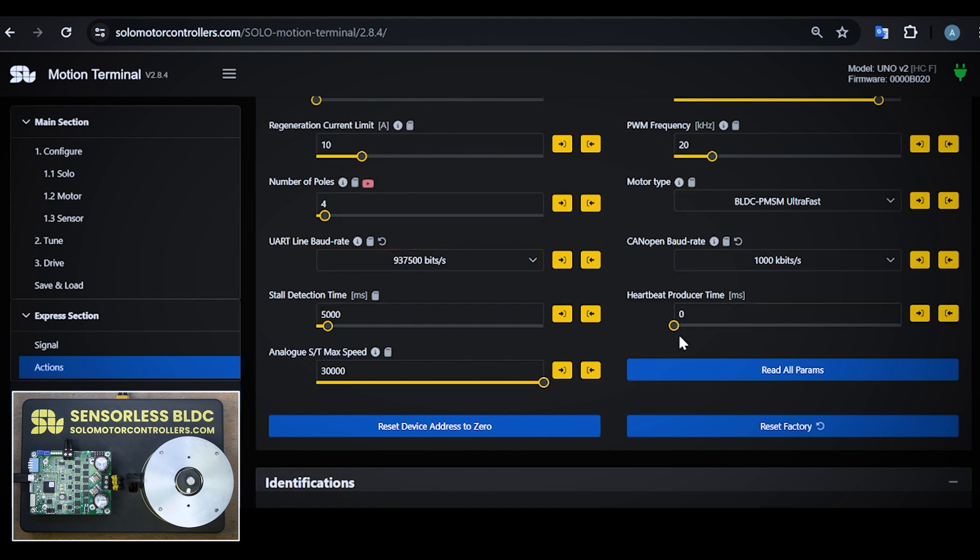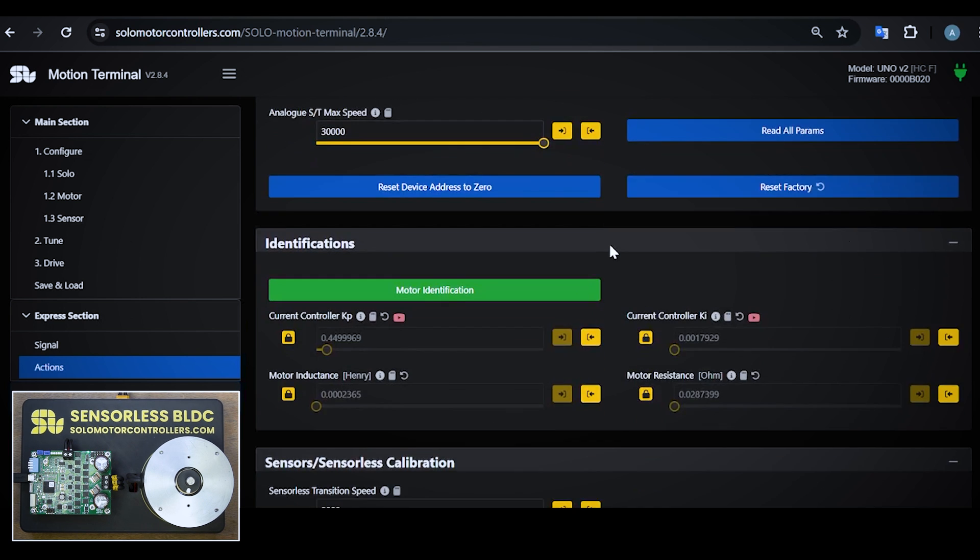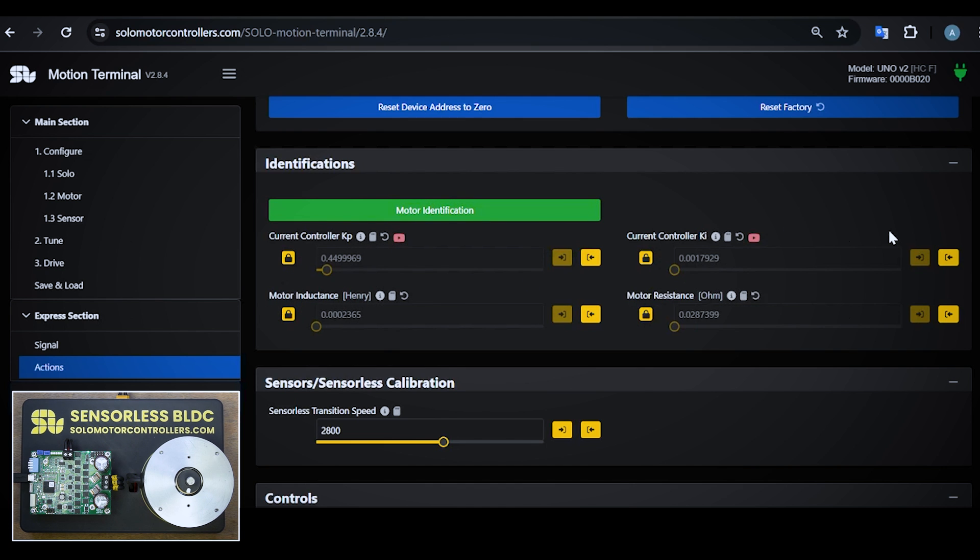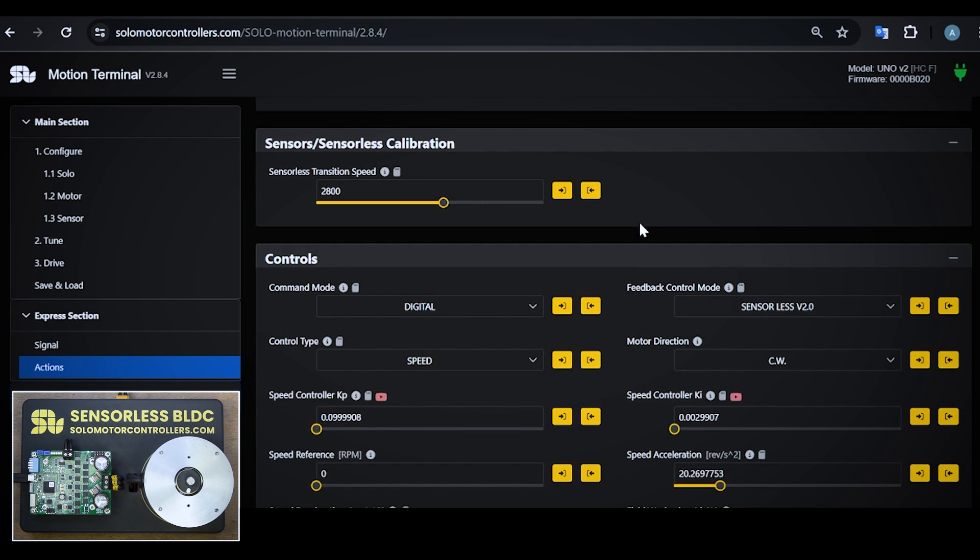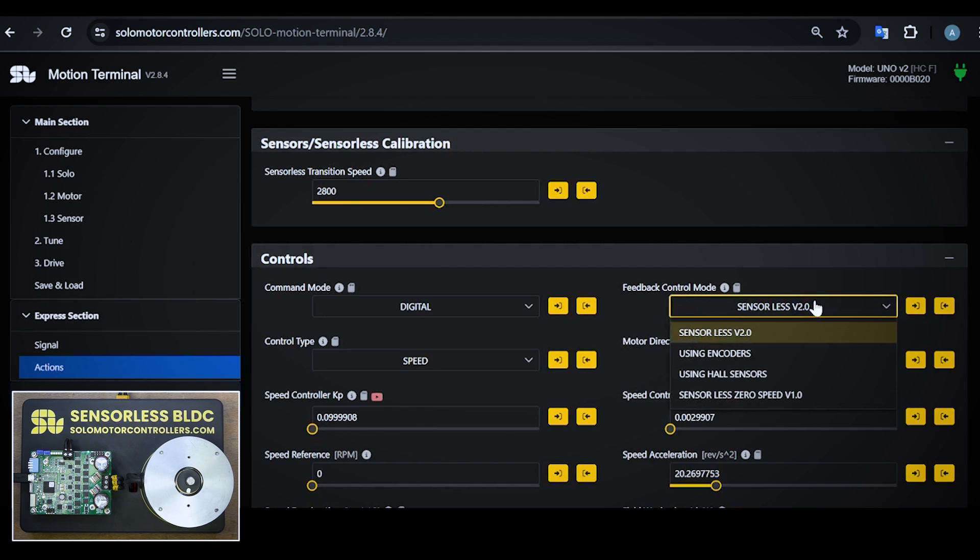Usually for motors above 2000 rpm you need to go with this option. The rest doesn't matter for sensorless control. Motor identification is something that we have done before one time by pressing this button. It just identifies these four parameters: current control gains and the resistance and inductance. And the most important part of the story is selecting the sensorless mode, so here in feedback control mode I've selected the sensorless control.